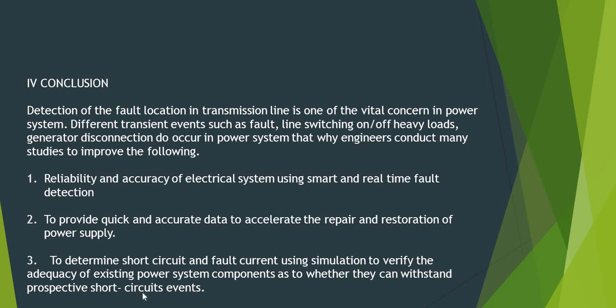Number 1 is reliability and accuracy of the electrical system using smart and real-time fault detection. Number 2 is to provide quick and accurate data to accelerate the repair and restoration of power supply. Number 3 is to determine the short circuit and fault current using simulation to verify the adequacy of existing power system components as to whether they can withstand a prospective short circuit event.